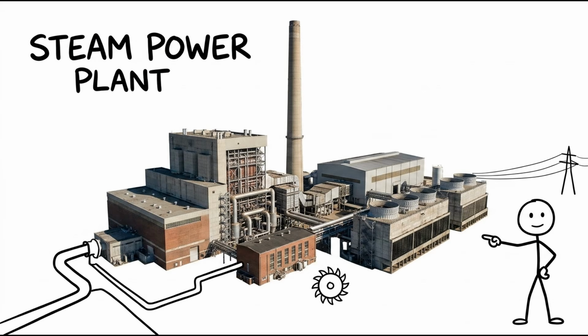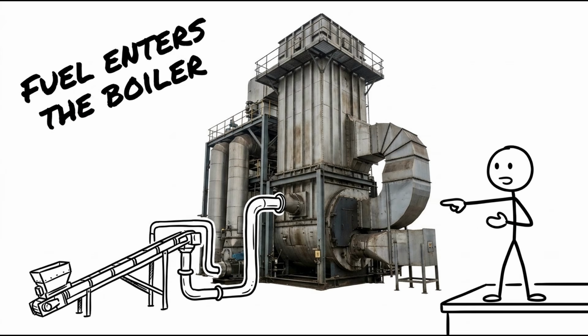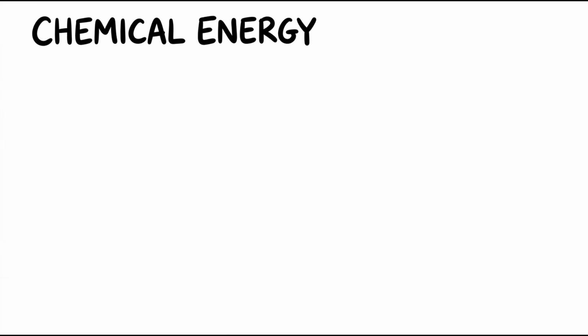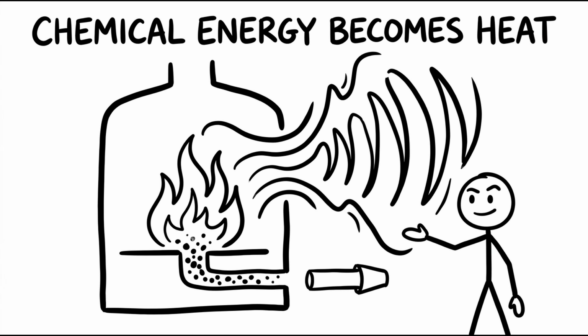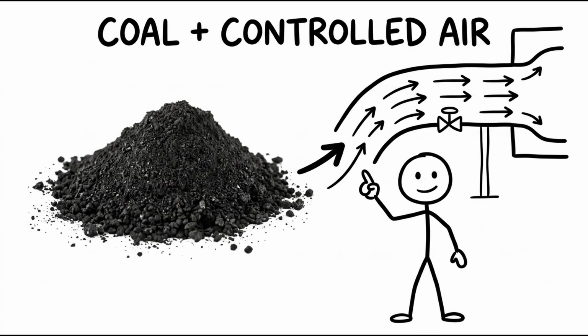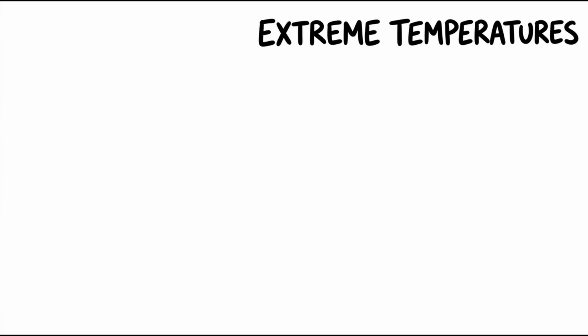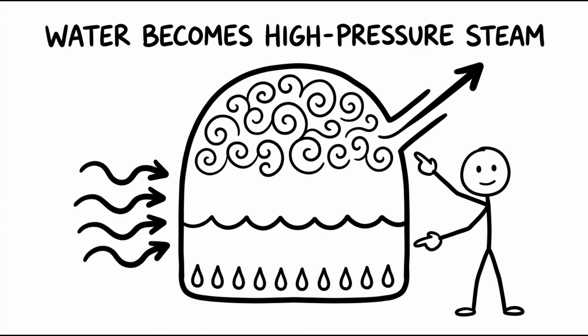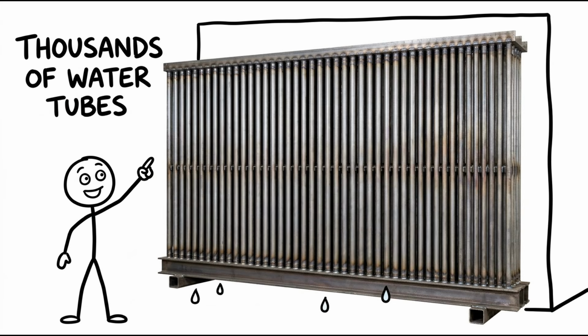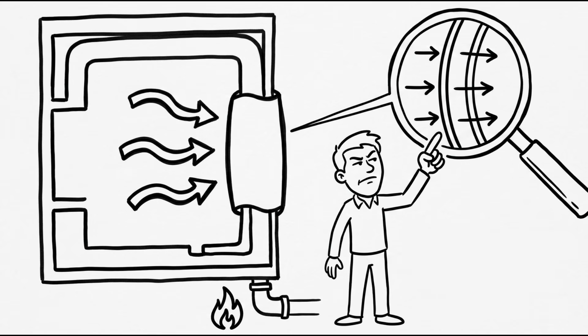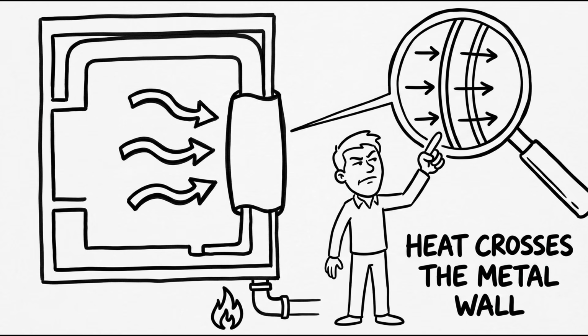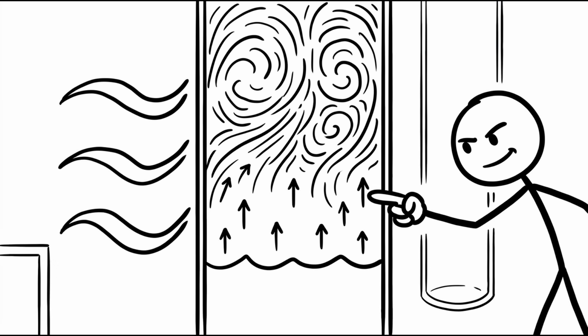At a conventional steam power plant, the prepared fuel enters a massive boiler or furnace. Here, controlled combustion releases chemical energy as intense heat. In a coal-fired plant, powdered coal mixes with carefully measured amounts of air and burns inside a huge furnace. Temperatures can become extremely high, producing enough heat to convert large quantities of water into high-pressure steam. The walls of the boiler are lined with thousands of tubes containing water. As the furnace releases heat, energy passes through the metal tube walls and heats the water inside them.